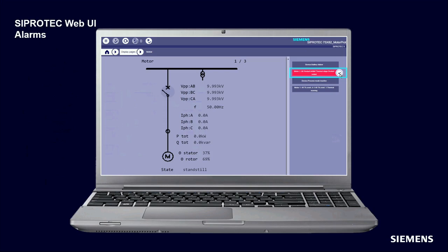First, we can show the screen of the relay and additionally alarms, which we define in the DIGSI 5, which we can acknowledge. For example, I ran over the restart inhibit temperature, and now this alarm is red because this signal is active, motor switched off. This remains red until the calculated temperature goes under the restart limit temperature, then it becomes green, and then I can acknowledge this signal, and then it becomes gray. So here is the possibility of having alarms which you can acknowledge.